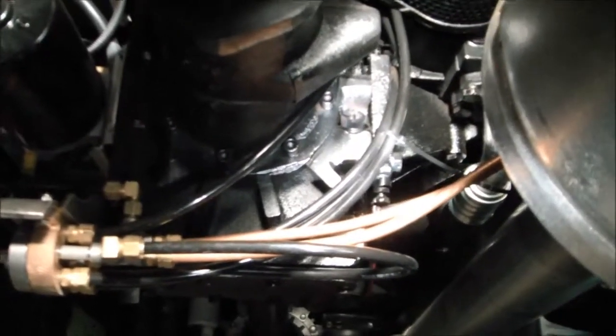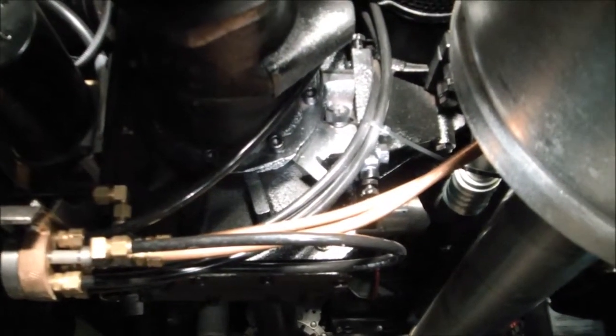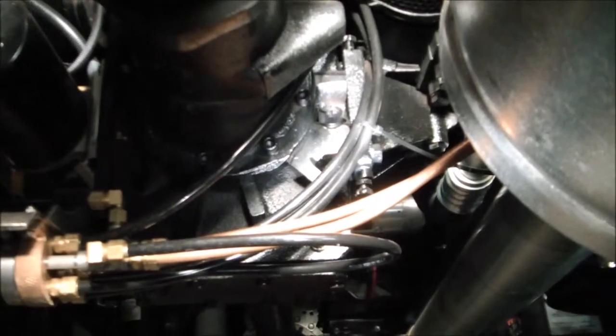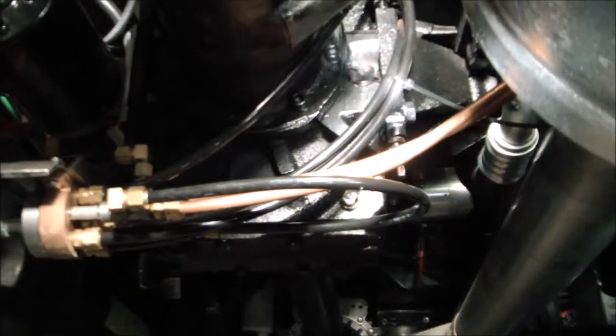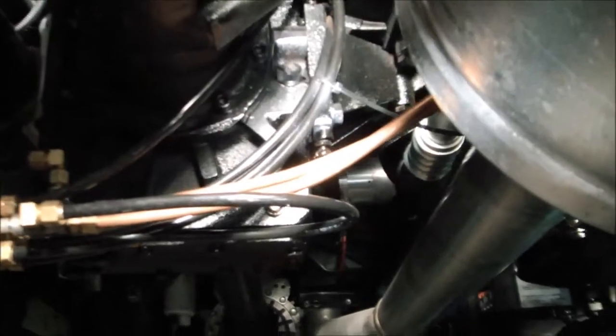Alright, today we're down underneath one of the gear cases of an LDMBC fire pump. The purpose of this video here today is to show you a couple of maintenance features, including how to check the oil level of the Darley pump gear case, as well as how to drain the oil of this LDMBC pump gear case. We'll start by showing you how to check the oil level.